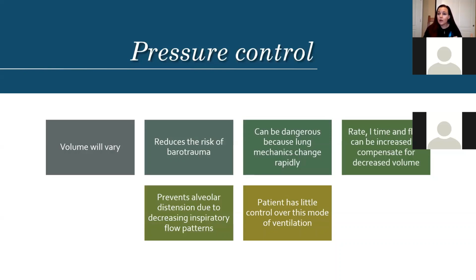So think about where your pressure alarm was set when you were doing volume control. Mine is always set 5 to 10 above, so normally it's going to be somewhere around 35 or 40, which means when you pick your pressure control number, that is a good place to start. Then you have to start looking at things like, is your ventilator PEEP compensated or not?